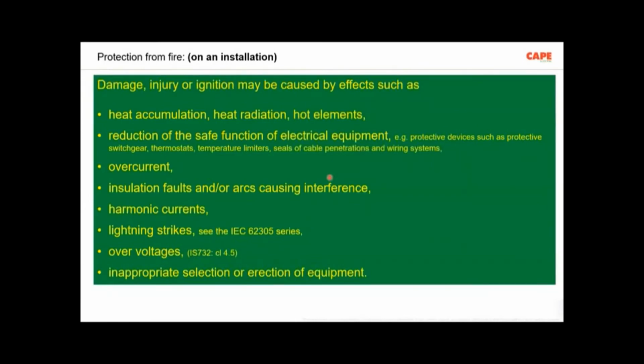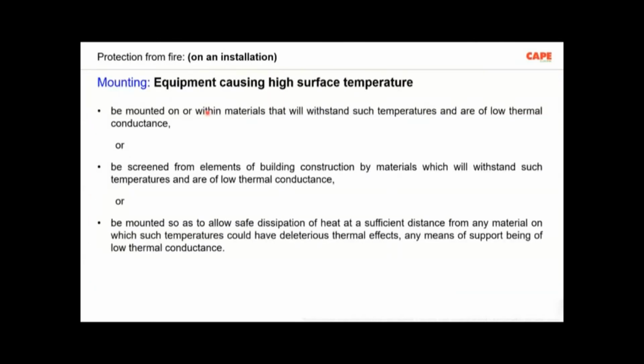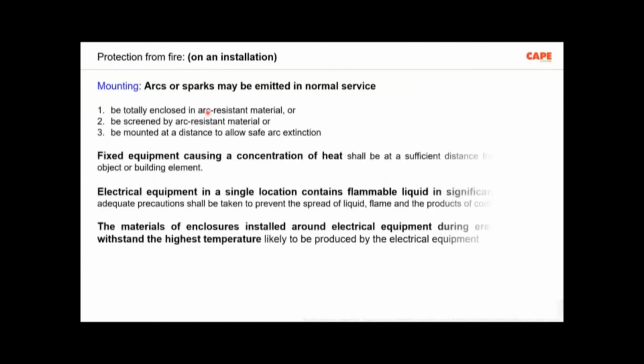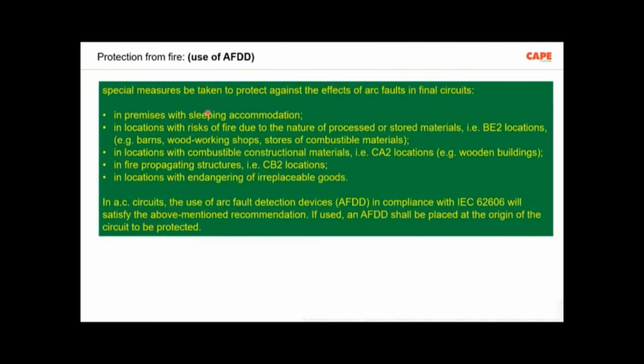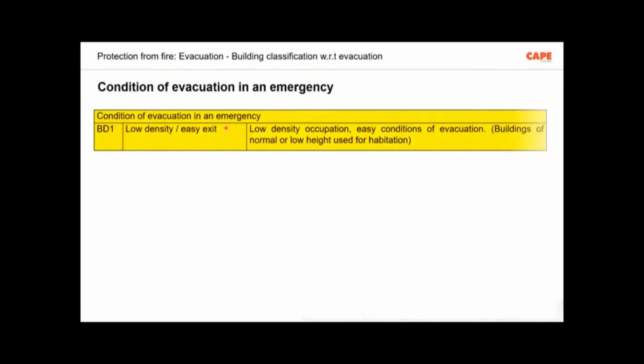Protection from fire of an installation, how does it arise? It is due to several reasons, such as heat accumulation, and I would like to skip this particular part. One of the reasons is that if you have equipment which is creating a temperature rise, you should take care of it and mount it appropriately so that the temperature rise is not creating a fire hazard. Mounting is important. Special protective devices such as arc fault detection devices are being recommended in the upcoming National Building Code, especially for premises with sleeping accommodation, that means the bedrooms or the hotel rooms. And in special cases, not everywhere, you need additional safety measures such as arc fault detection devices.